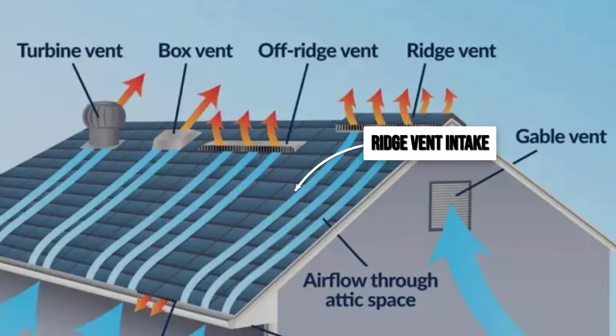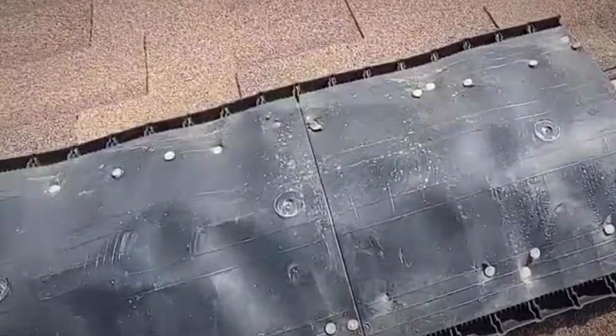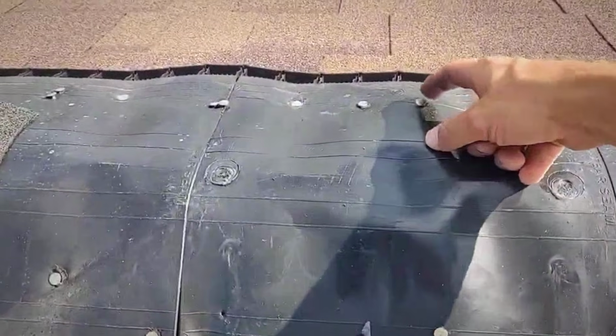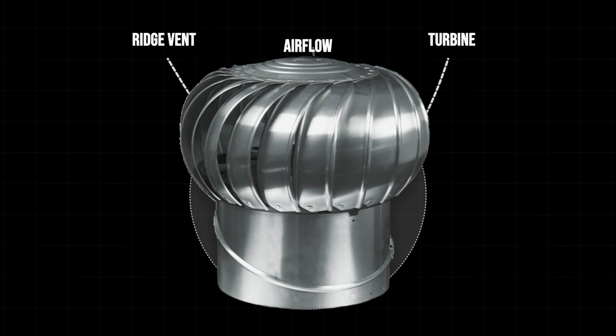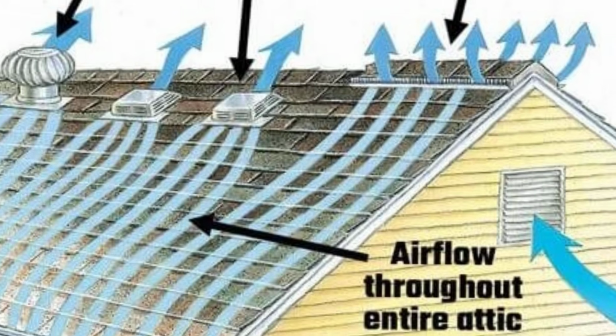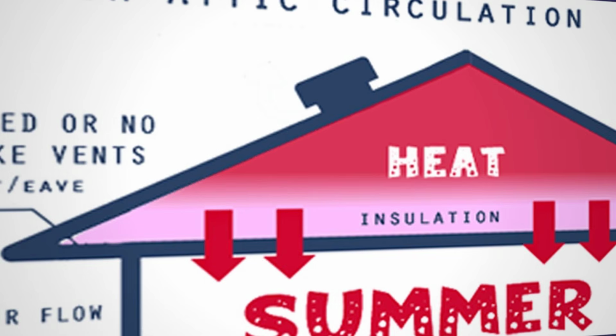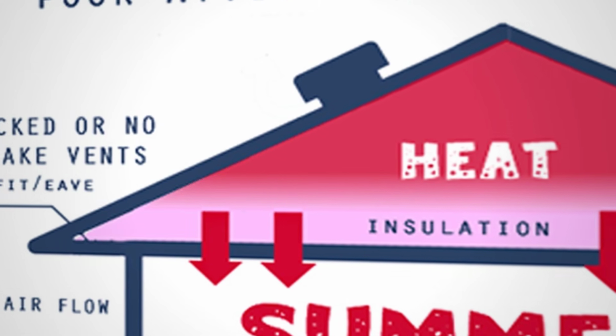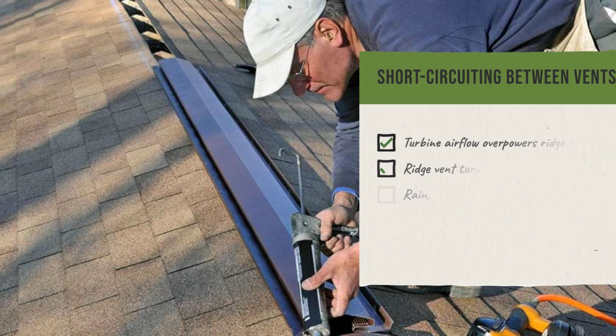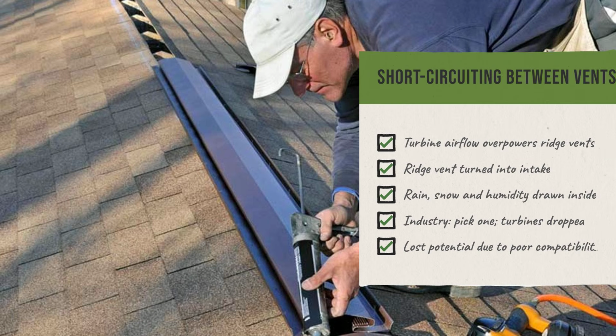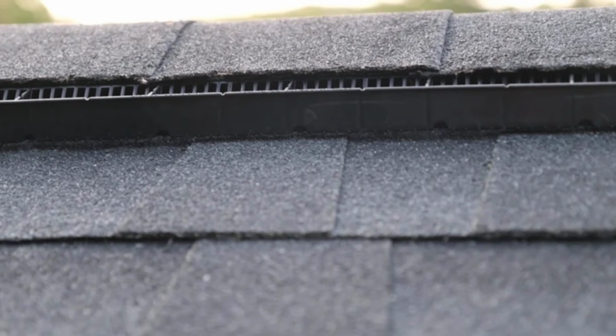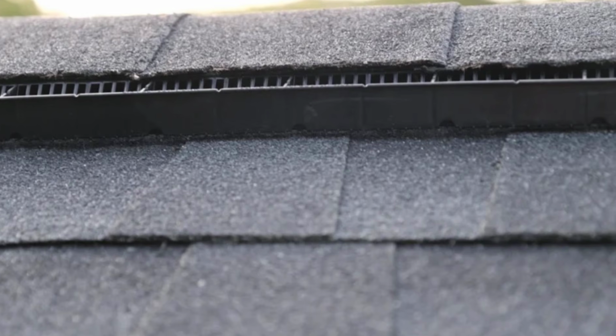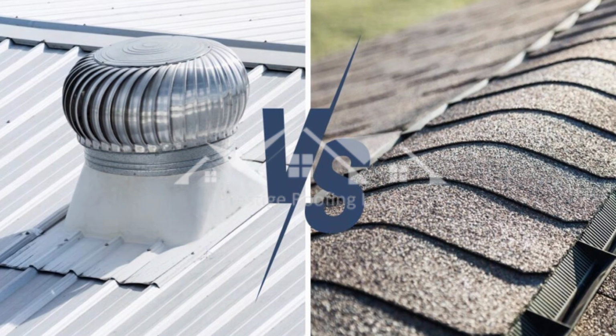The second weakness was a phenomenon called short-circuiting. This occurred when a turbine ventilator and a ridge vent were installed simultaneously on the same roof. Because the turbine pulled air more aggressively than a passive static vent, it could reverse the airflow through the ridge vent, drawing outside air inward, along with rain, snow, and humidity, instead of exhausting warm air out. The industry response at the time was simply to tell installers to choose one system and commit to it. And because ridge vents were passive, simple, and required no moving parts, the turbine was consistently the one that got eliminated.